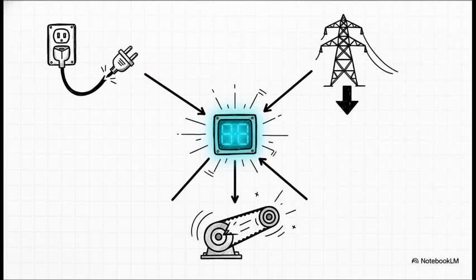You know, to truly master diagnostics, you really should know how to deliberately trigger faults in a controlled environment. It's the best way to test your setup. For example, to simulate an SLF1, which is a Modbus communication interruption, you can quite literally just unplug the network cable from the drive. Bam, fault triggered.